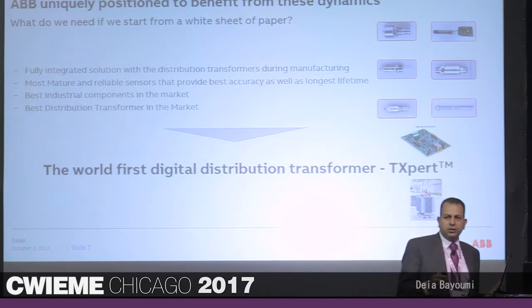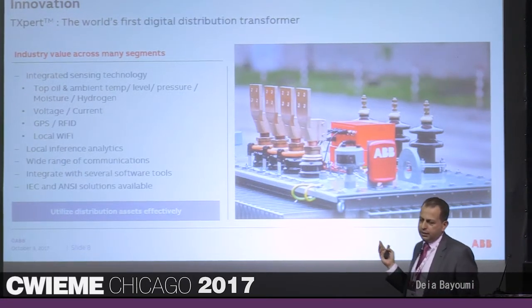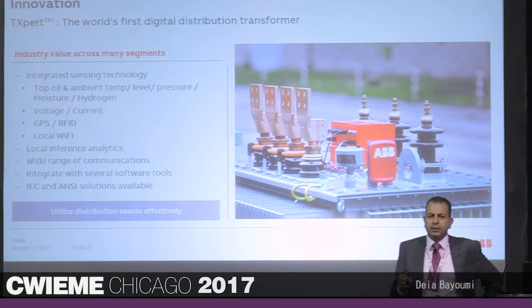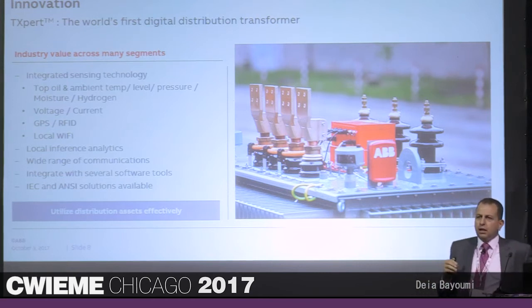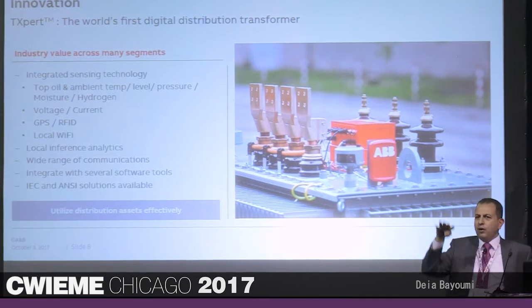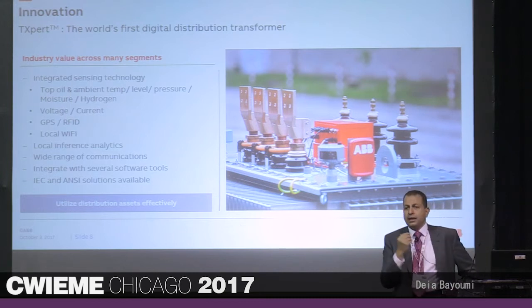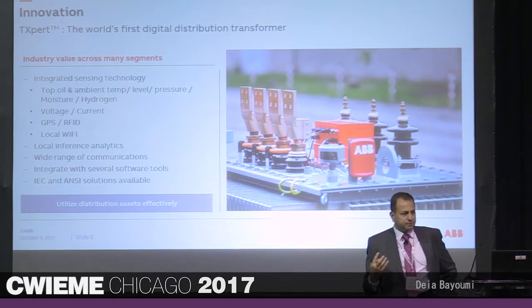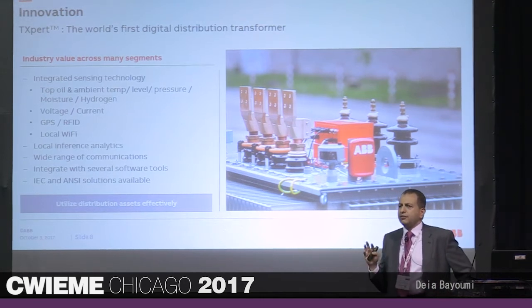We're not just writing static calculations — we start doing more predictive analytics that make sense for the transformer and for the grid around it. Coupling all of this together inside the transformer is when we launched this new digital distribution transformer. This is the first release we had in March this year. We have pilots around the globe tested in different applications. Hardware-wise, we start looking at oil temperature, ambient temperature, oil level at low and critical levels, pressure buildup inside the tank, moisture, and hydrogen — the values we thought we really need to monitor for distribution transformer level.